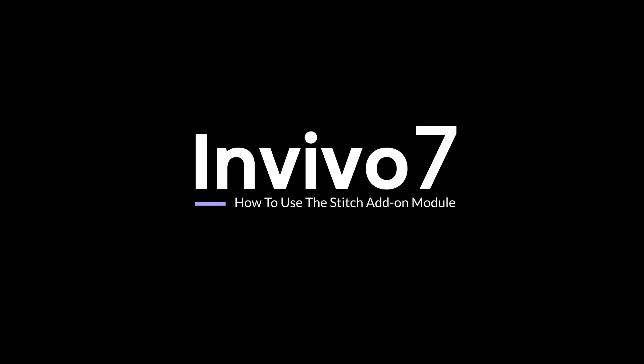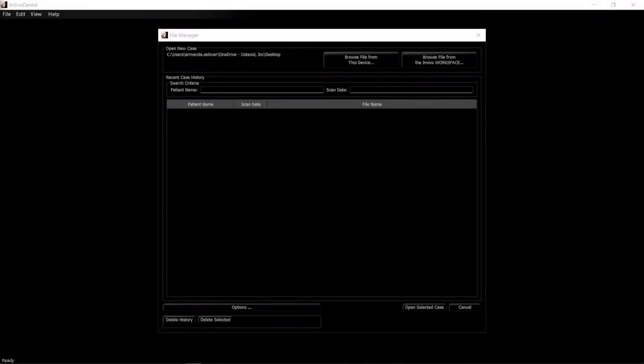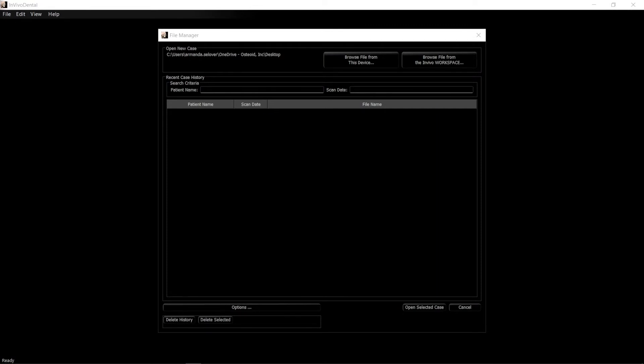How to use the STITCH add-on module. The purpose of the STITCH add-on module is to combine two DICOM datasets. This is helpful for scans that need a longer Z-axis than the CBCT scanner is capable of. Be sure to overlap the two datasets for proper registration.